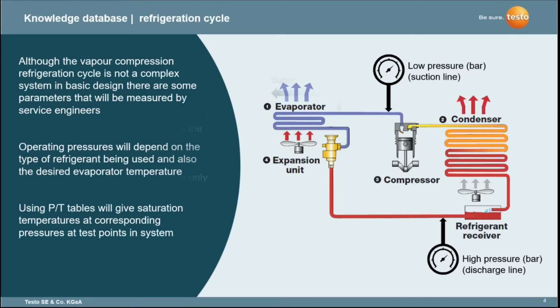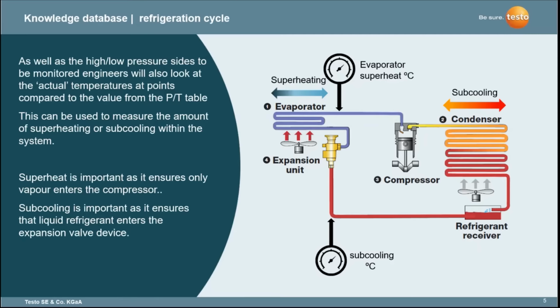Additionally, what engineers are typically looking for, as well as the theoretical saturation temperatures, is the real temperatures coming out of the evaporator and condenser, and being able to use those to do the calculation of the amount of superheating or subcooling that's going on within the system. So it's really this combination of monitoring temperatures and pressures simultaneously that manifolds are used for.